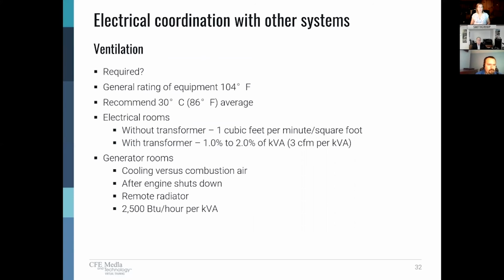So really, when you're talking to your HVAC engineer, you first need to establish the fact that whatever we do to this room, we need to keep it below 104 degrees. Now, second thing is you don't really want your maintenance people working at 104 degrees or 103 degrees, right? So there has to be some reasonable discussion, particularly if they're critical large power rooms, about what would be a maximum temperature that you would want maintenance and operations people to work in. Maybe that's 80 degrees, maybe it's 78 degrees. Again, it's a discussion with the client and their maintenance staff as well. So we generally recommend about 86 degrees maximum average, but it may be lower or higher.